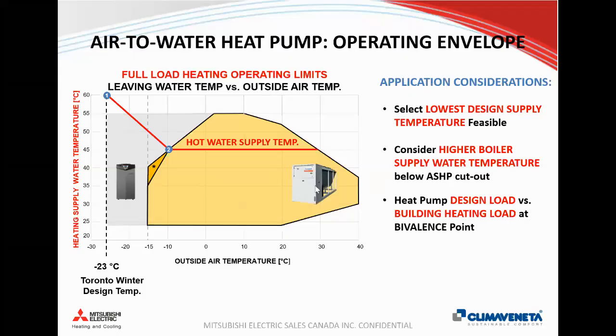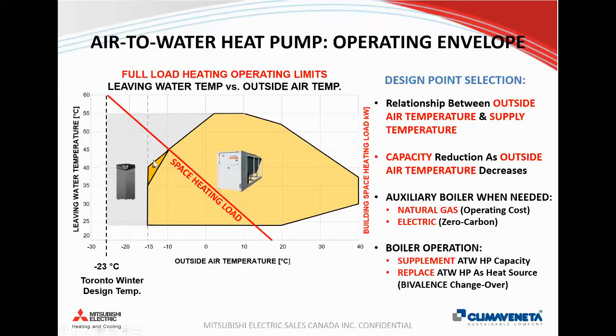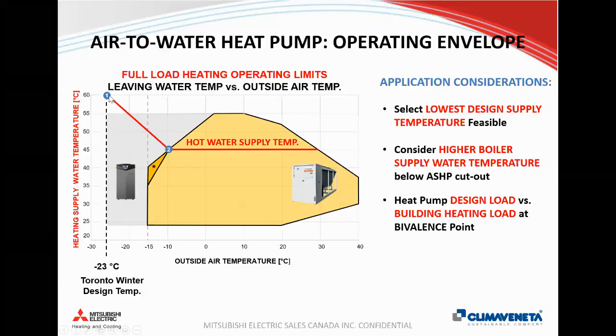So if we look at supply temperature for the system, most of the time when I'm talking to engineers, they'll say, well, 45 degrees Celsius isn't hot enough of a temperature to meet the heat loads in the heat emitters in the building. But it's important to recognize that you're comparing that to a design temperature at a much colder outside air temperature. Because of the relationship between the space heating load and outside air temperature, chances are you don't necessarily still need that same high supply temperature that you're using at minus 23 in this example. And in boiler systems, this is the reason we use outdoor air reset strategies, because as it gets warmer, we don't necessarily have as much heat loss from the building. So we're basically just trying to operate our heat source to match that heat load as it gets warmer outside.